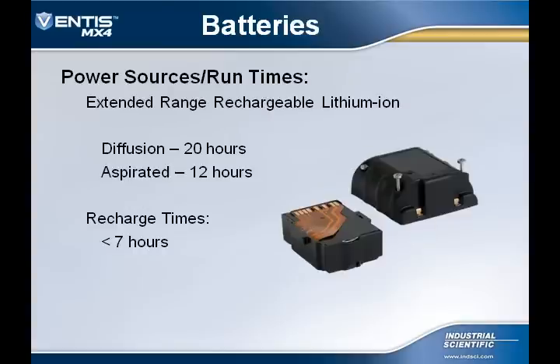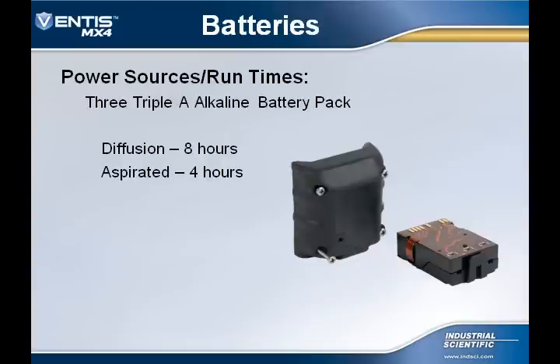The Ventis MX4 also has an extended range rechargeable lithium-ion battery. It has a runtime of 20 hours for the diffusion configuration and a 12-hour runtime for the aspirated configuration. Charging this lithium battery will take less than 7 hours. The Ventis MX4 can also use 3 replaceable AAA alkaline batteries. It has a runtime of 8 hours for the diffusion configuration and 4 hours for the aspirated configuration.